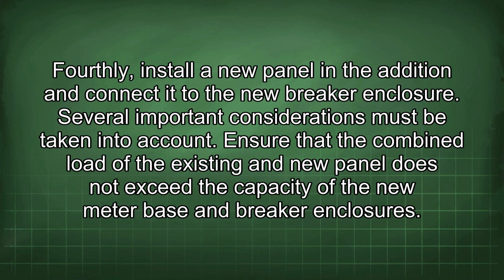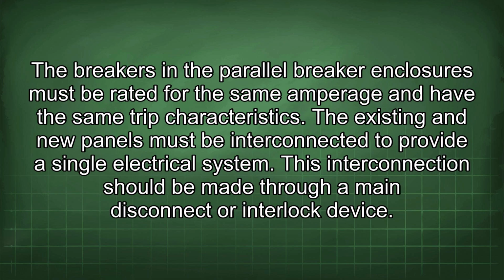Several important considerations must be taken into account. Ensure that the combined load of the existing and new panel does not exceed the capacity of the new meter base and breaker enclosures. The breakers in a parallel breaker enclosure must be rated for the same amperage and have the same trip characteristics. The existing and new panels must be interconnected to provide a single electrical system. This interconnection should be made through a main disconnect or interlock device.